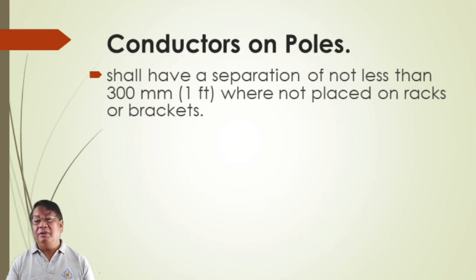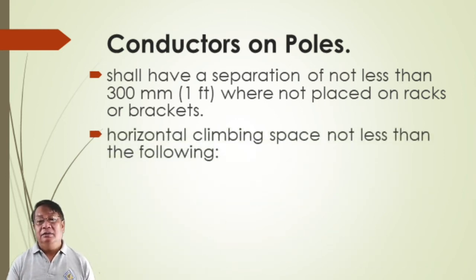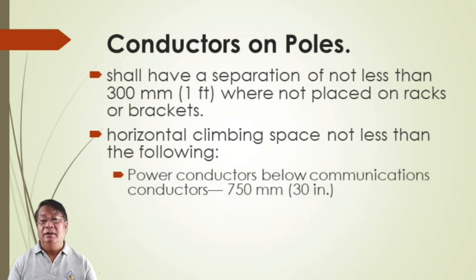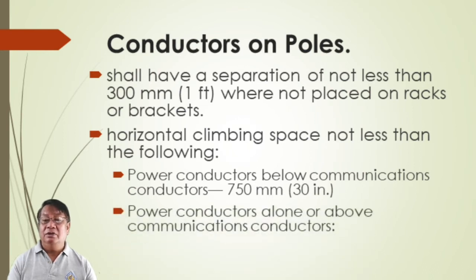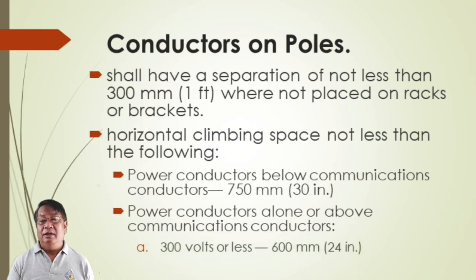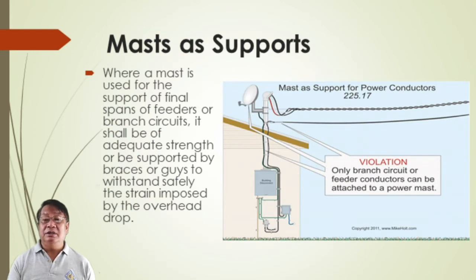For horizontal climbing spaces, power conductors below communication conductors shall be at least 750 mm so that they will not affect the communication channel. Power conductors above communication conductors at 300 volts or less require 600 mm separation; over 300 volts, 750 mm separation.